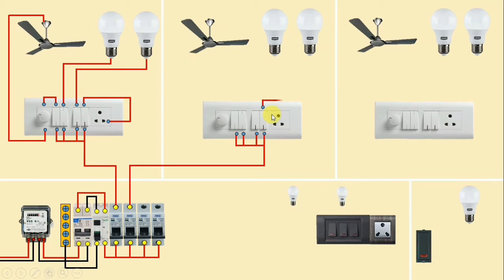So you repeat the same thing in this room too - the socket outlets should have a dedicated miniature circuit. It's best to have all sockets connected together in one loop. Since it's a three-bedroom flat, you connect all the sockets to one line, or if there were four rooms, you might connect two rooms to one miniature circuit breaker.